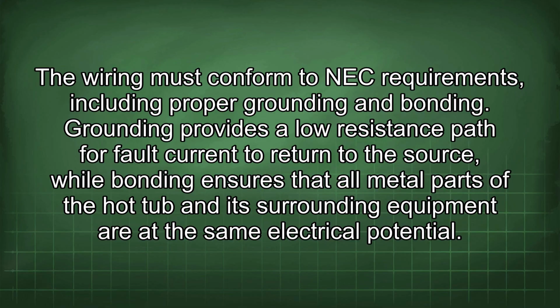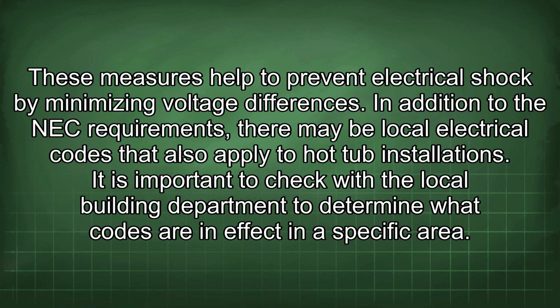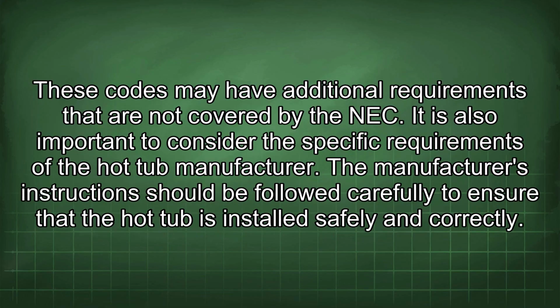Grounding provides a low-resistance path for fault current to return to the source, while bonding ensures that all metal parts of the hot tub and its surrounding equipment are at the same electrical potential. These measures help to prevent electrical shock by minimizing voltage differences. In addition to the NEC requirements, there may be local electrical codes that also apply to hot tub installations. It is important to check with the local building department to determine what codes are in effect in a specific area. These codes may have additional requirements that are not covered by the NEC.